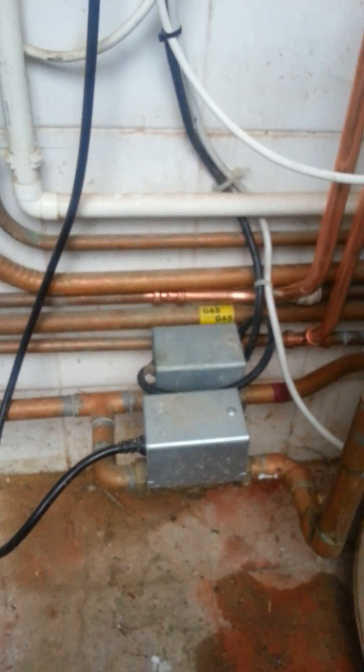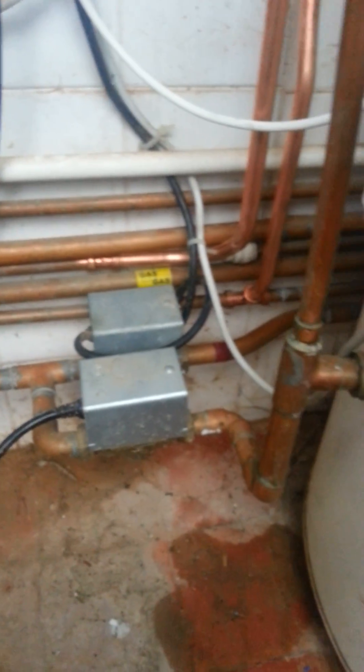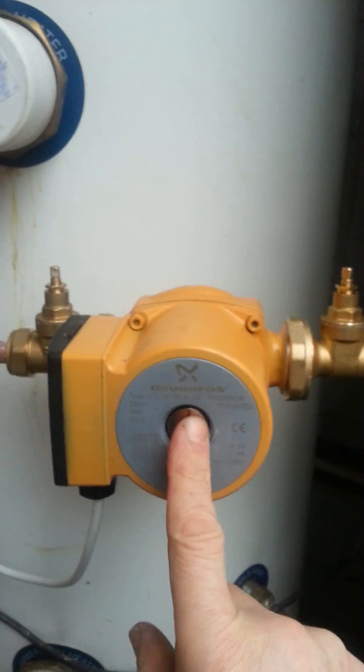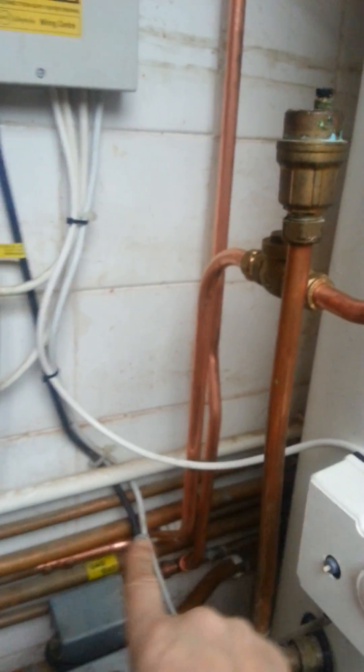So this valve and this part of the system becomes useless to us. What I needed to do was find some way of heating the hot water up. So what I've done is I've gone into the return to the cylinder, added in a Grundfos pump and anti-gravity valve, come round up into the cold feed into the boiler.